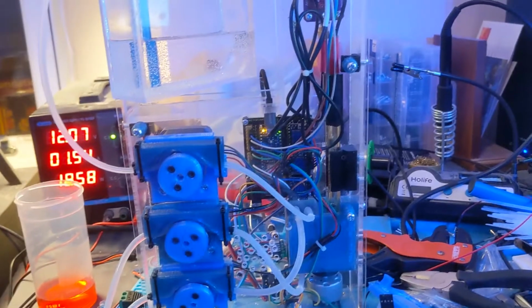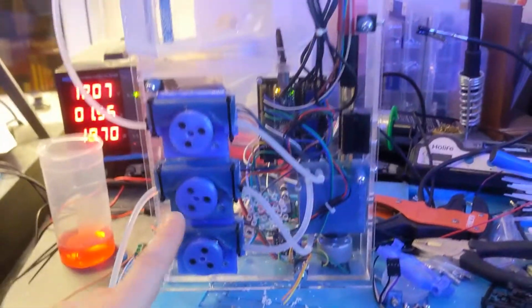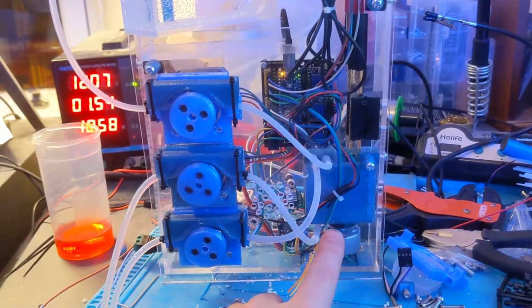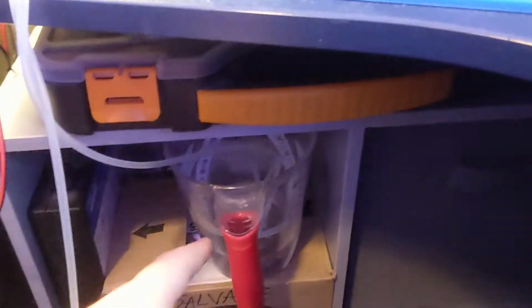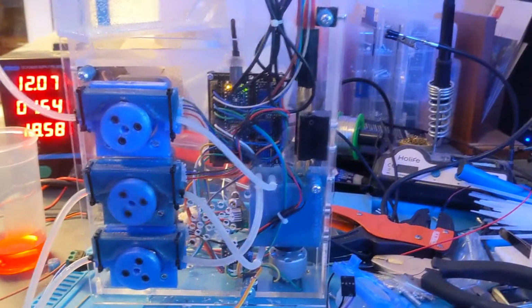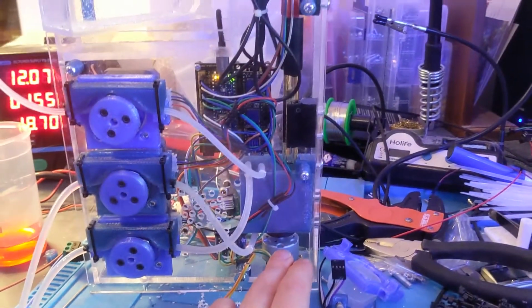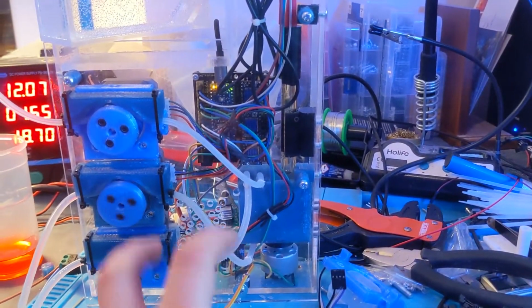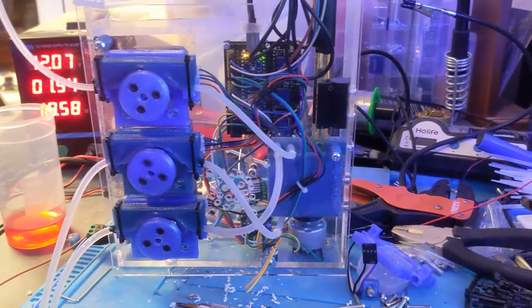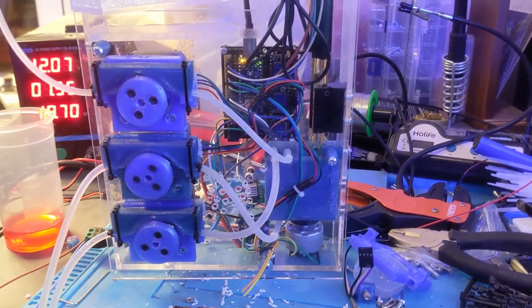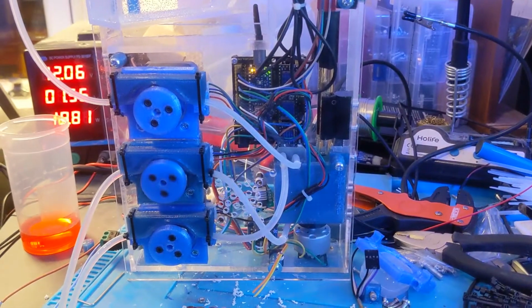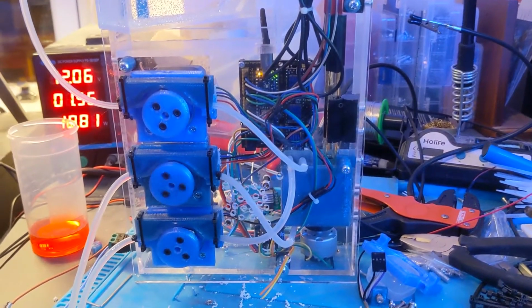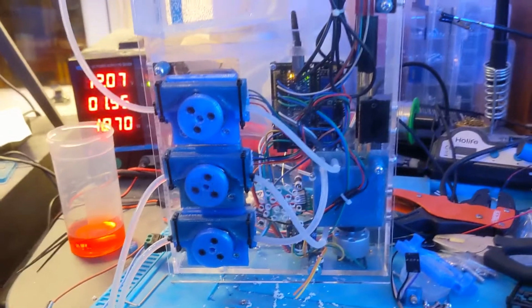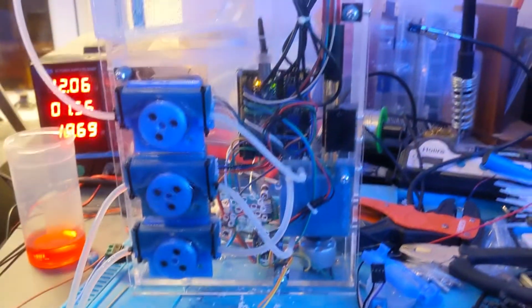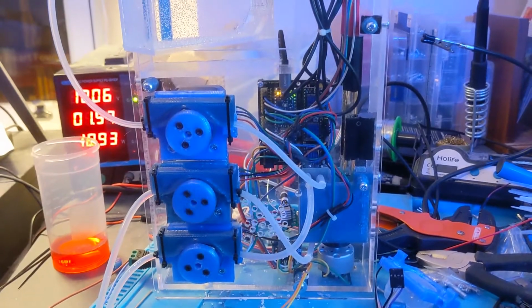which should be dealt with by leaving it a bit longer between tests, because what it's going to do now at the end, it's going to empty out the reaction chamber there. It's going to fill it again from the tank water. It's going to run the stirrer a bit to just agitate everything, and it's going to leave that water there, so that you give it an hour, and any residue that's on that pH probe will theoretically just disperse into that water, which will then be purged out, rinsed, and replaced with the next test.